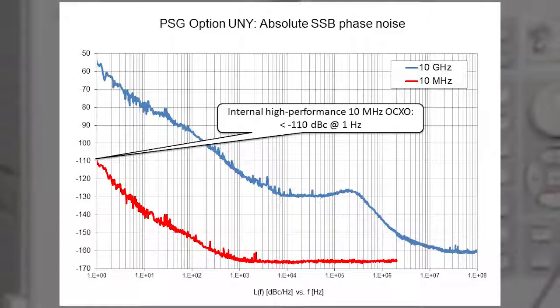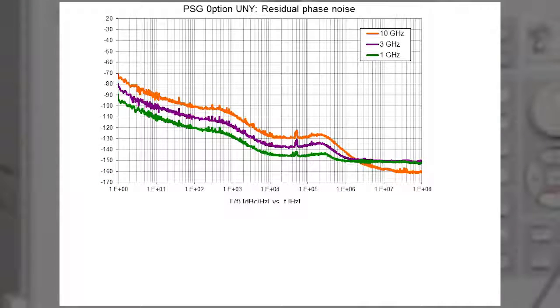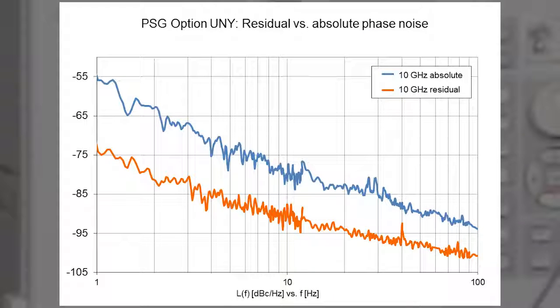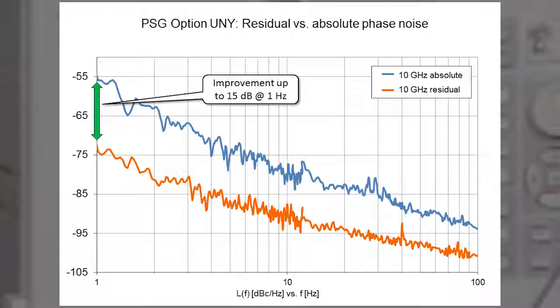However, if you have a 10 megahertz reference that is cleaner, you can improve the PSG phase noise even more. In the PSG data sheet, we provide plots and specifications for residual phase noise. This 10 gigahertz plot illustrates the potential phase noise performance that the PSG can support if you provide an ideal, extremely clean 10 megahertz reference.